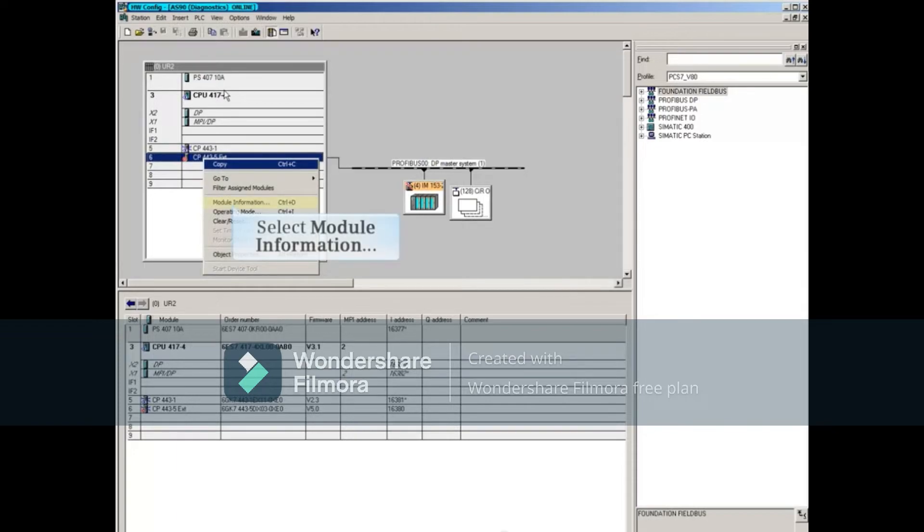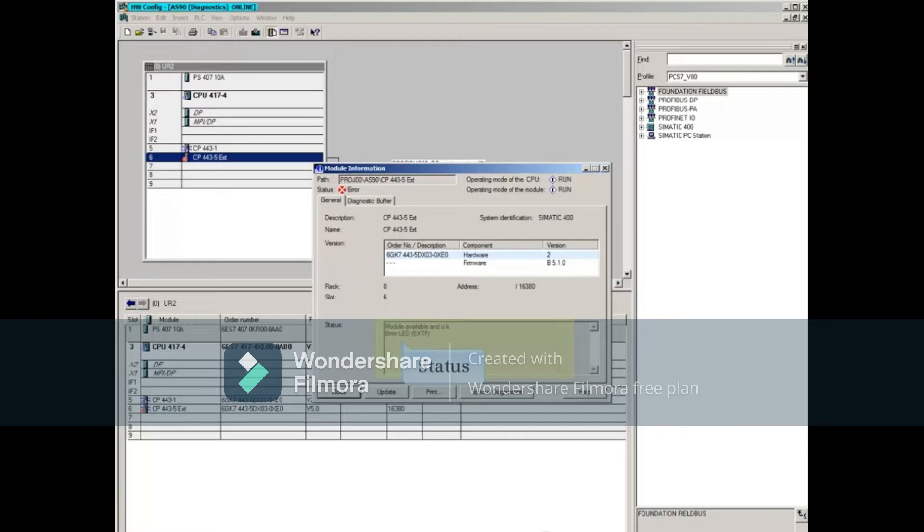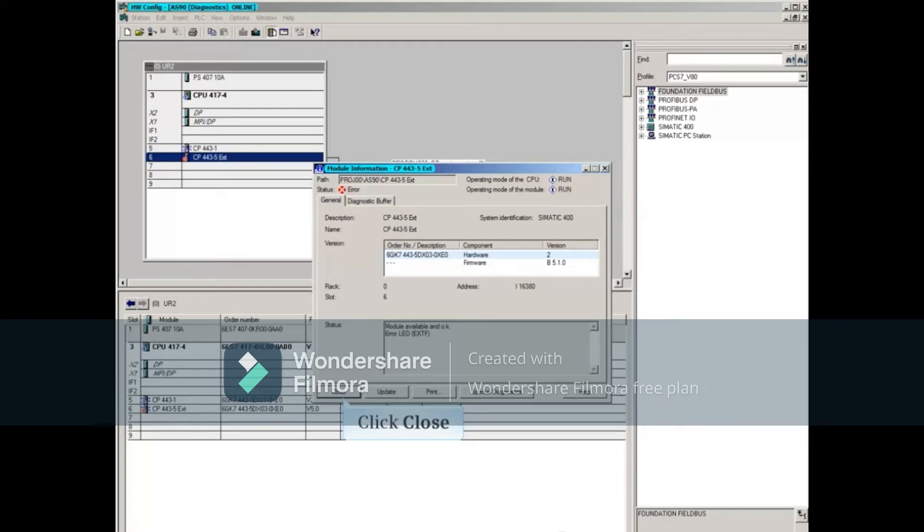Right-click the PROFIBUS communication processor, and open the Module Information window. Notice now that the CP module shows an OK status with its external fault LED lit. There are no current diagnostics, so close this window.